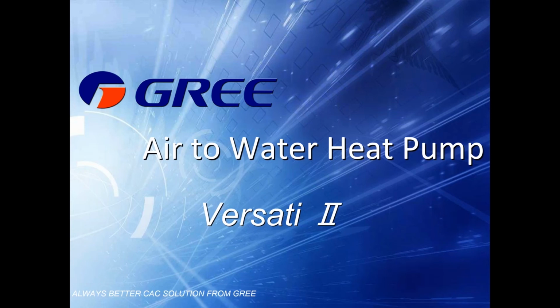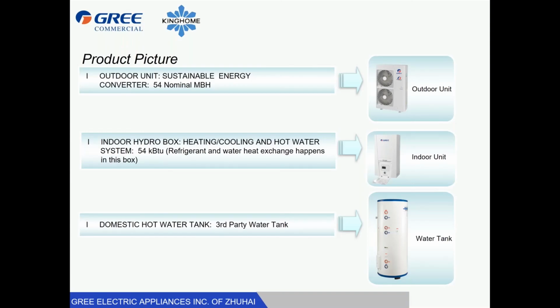Since heat pumps are getting such a strong emphasis in the code this year, we feel that it would be important to take a look at water heat pumps. So this is a split system. The outdoor unit is a 54 MBH nominal capacity, and it connects to an indoor unit that has a water to refrigerant heat exchanger. And then you can connect it to a third-party water tank if needed.